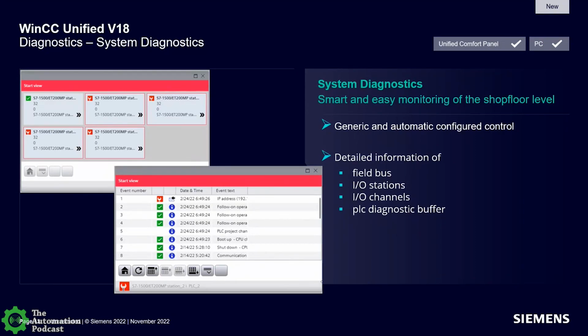And it is visual inside TIA Portal when I'm online. I see the same graphics and see the same alarms read from the PLC. And it's fed to the HMI object that might be configured in the project. It's fed to the web server of the PLC, and it's on the display of the main S7-1500 PLCs. And it's also published in the OPC UA diagnostics buffer.